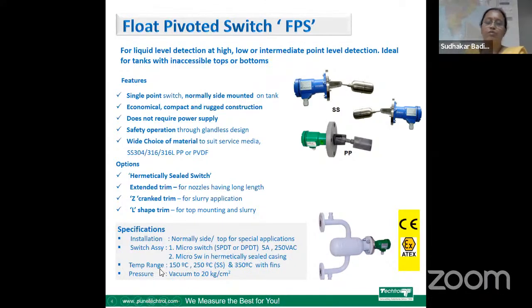The switch is suitable for temperature range up to 250 degrees Celsius, and 350 degrees Celsius option is also available with radiating fins. It is suitable for pressure up to 20 kg per centimeter square. So on the right hand side, you can see the pictures of level switches with stainless steel material and PP material. At the bottom, you can see this level switch is mounted with external chamber for the tanks having stirrers or turbulent liquids.